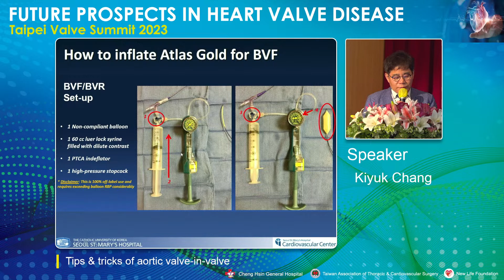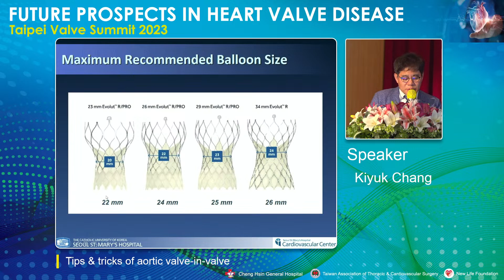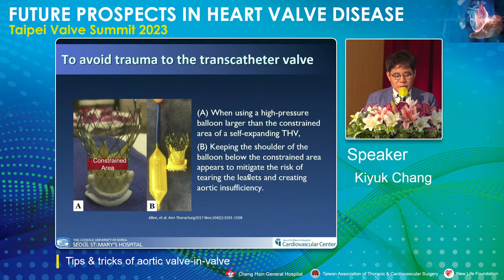In case of Evolut implantation at the time of valve fracture, you have to remember the constraint area. So in case of a 23 millimeter Evolut R implantation, the constraint area diameter is 20, so the maximal recommended balloon size should be less than 22 millimeter. Another consideration: when using a high pressure balloon within the constrained area of a self-expandable TAVR valve, keeping the shoulder of the high pressure balloon below the constraint area prevents the risk of tearing the leaflet.